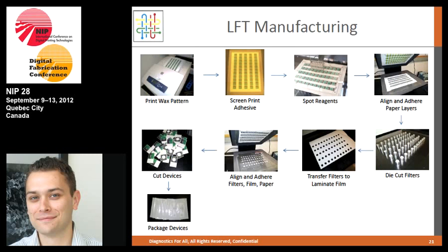For manufacturing: we start with wax printing, then heat it as described. We screen print adhesive. The liver function test has two layers of patterned paper, two layers of laminate, and a blood cell filter. We spot reagents using a Biodot robotic spotter — inkjet printing technology could also work. A simple jig aligns the two paper layers, filters are die-cut and transferred to lamination, everything is sandwiched, laminated, cut, and packaged. Right now at small scale we make about 500 devices per day, enough for field tests and clinical trials. We've chosen techniques that are highly scalable and could produce tens of millions of devices.